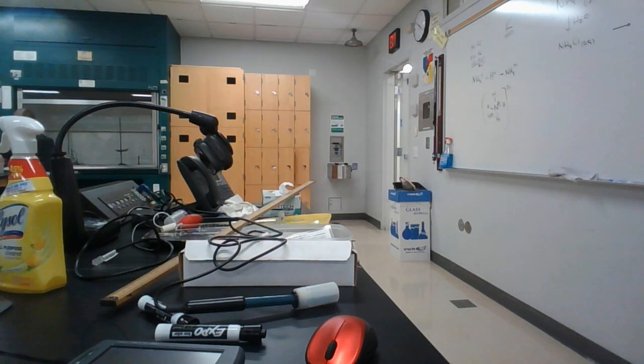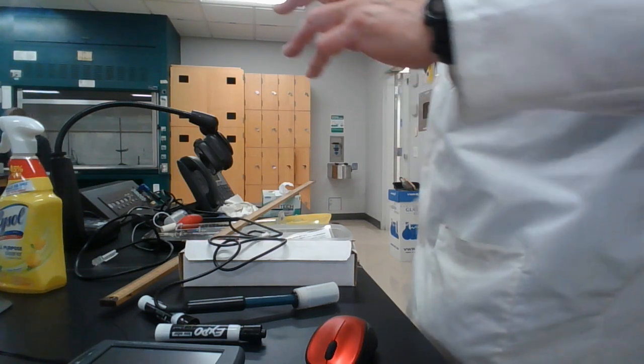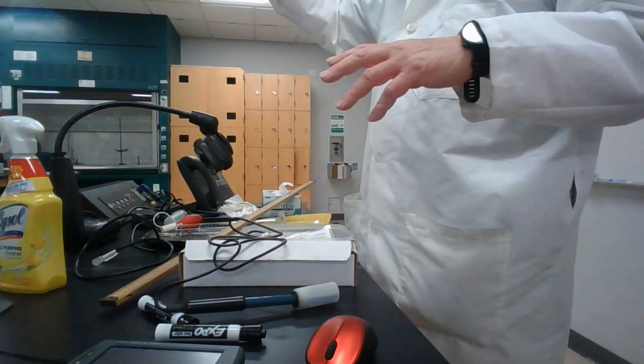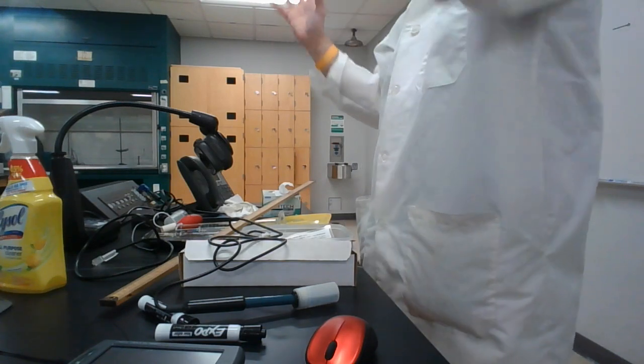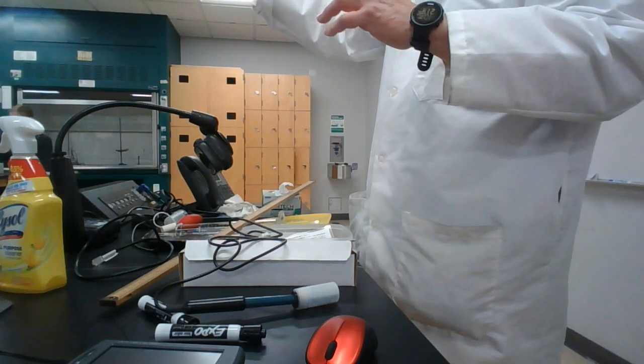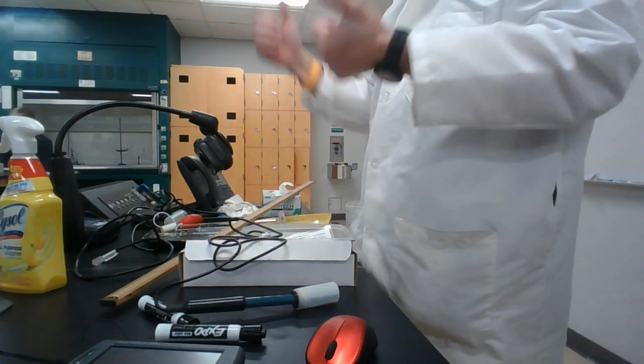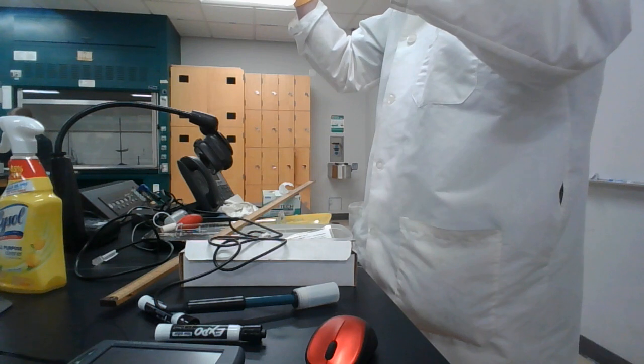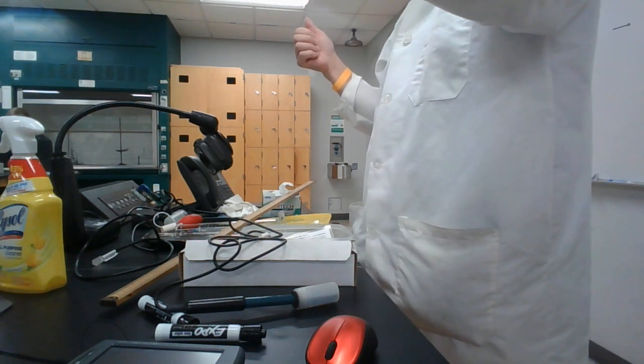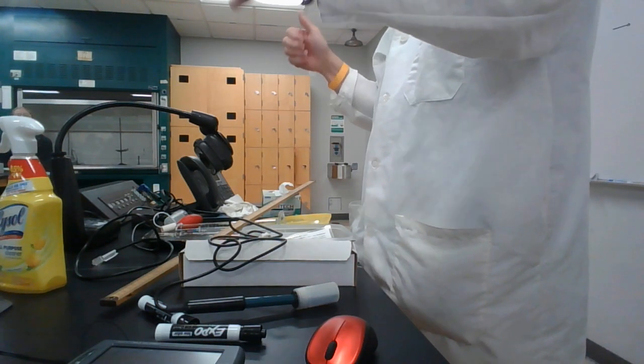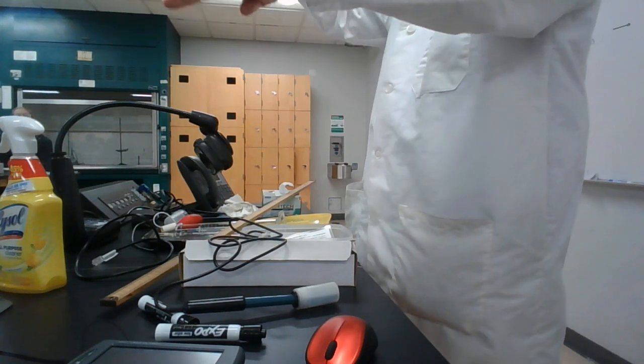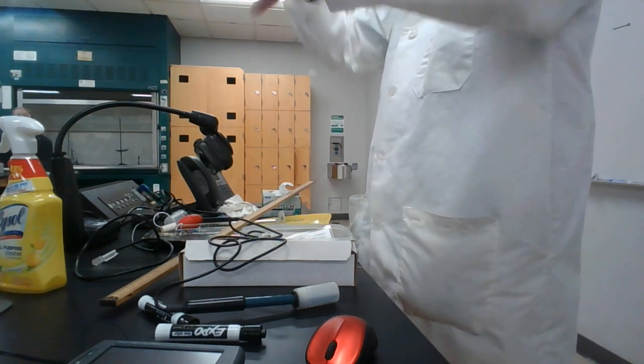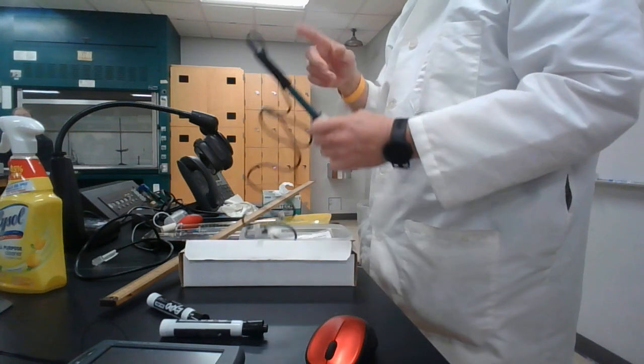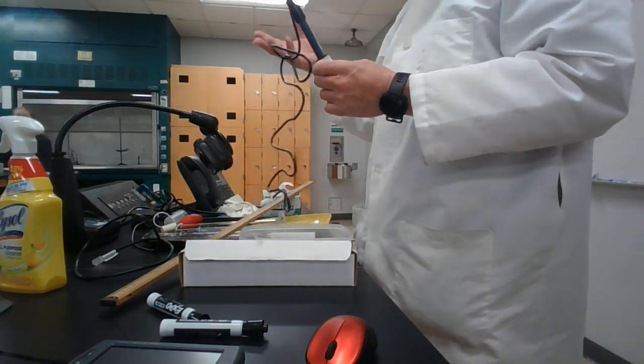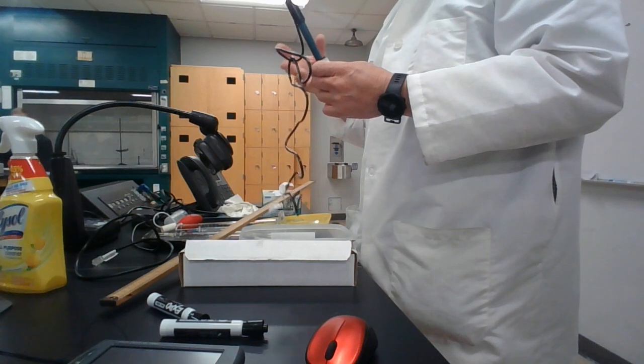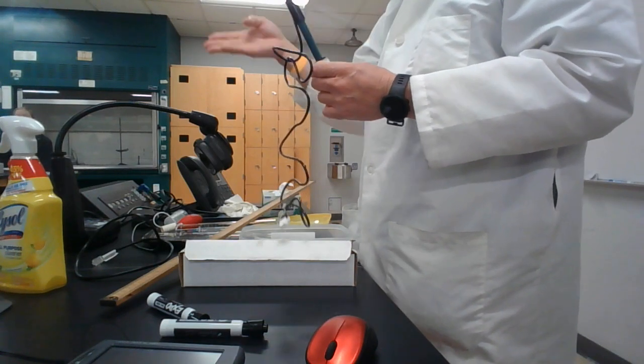And so what can happen is this. Let's say you get a bunch of hydronium collecting on the outside of this. What that's going to do is, if a whole bunch of hydroniums are collecting on the outside of the glass, that's going to increase the positive charge on the outside. On the inside, there's a fixed amount of positive charge and a fixed amount of negative charge. And so whenever we have a difference in charge, it creates something called a voltage. And what we're measuring is the voltage. The voltage is very small. It's millivolts that we generate. But what we can do is we can calibrate the millivolts to a pH reading.